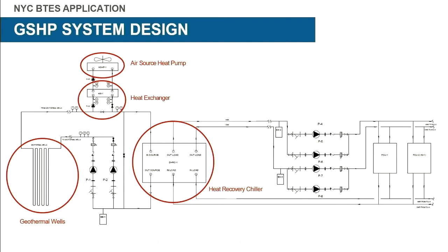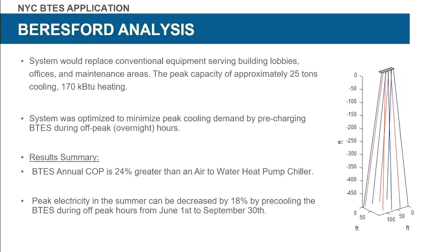And the way the system is designed to work is that it's going to operate as a standard ground source system for the majority of the year. But during peak cooling conditions, it helps serve this cooling dominant area by storing up or preconditioning the loops during overnight periods. And this will provide, we're modeling an 18% reduction in energy during peak cooling.